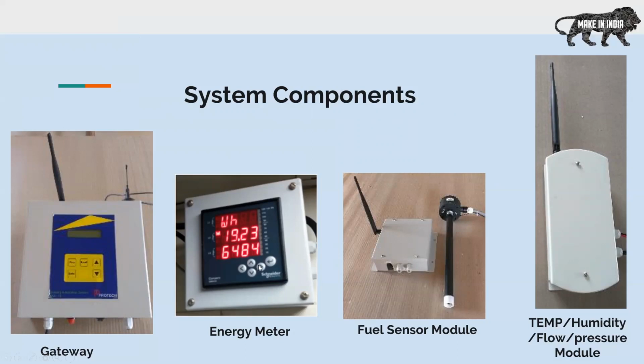Then this is the energy meter module. If a client has an existing energy meter, we can integrate with it using RS485. Otherwise, we provide a separate energy meter with the required CT coil, the connecting cables, and the enclosure. Then this is the fuel sensor module for diesel pump or DG. This rod is custom manufactured based on the height of the tank. Then this is the temperature, flow, pressure module.